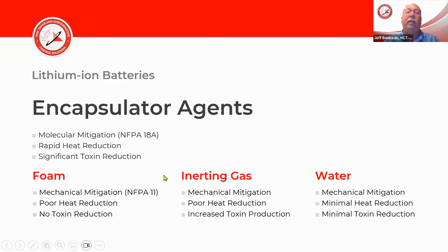I've talked about the huge impact this can have across applications, in warehouses, homes, buildings, offices, schools. Look at the ability to mitigate rapid heat reduction, and the differences between the agents out there versus encapsulator agents. Foams, under NFPA 11, don't work on a 3-dimensional flowing liquid fuel fire or gas fire, but an encapsulator agent does, with poor heat reduction from foam. The foam blanket breaks down, and when it does, heat, fuel, and oxygen are present again, so you get reignition. We also have to worry about toxins.